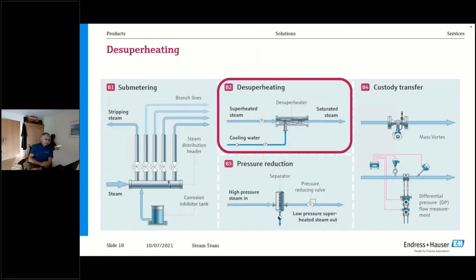Now we're going to talk about desuperheating. So what's done in desuperheating? You send superheated steam in and you get steam at a lower temperature out. So in the US, it's often called an attemperator. And you reduce the temperature of that steam by adding cooling water. What's the reason? Typically, you have a lot of applications where you have steam at a high temperature available, but you need steam at a much lower temperature and pressure. And there, this is the perfect solution.